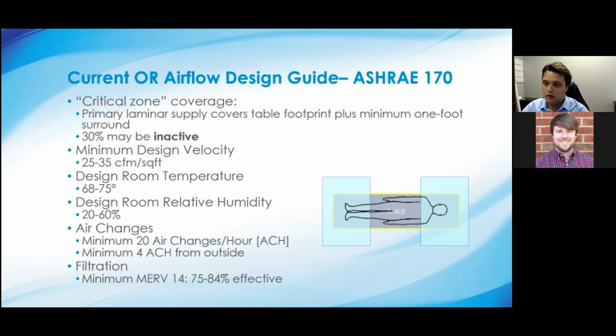Now, where did that 30% come from? How do you know that if you have 30% inactive, you're still safe? Honestly, your guess is as good as mine. I've never seen any backing of why 30% is acceptable, how that impacts patient safety or anything. It's kind of pulled out of a hat. That's the first point here, indicting the ASHRAE 170 code for not necessarily being best practice. It is a design guide. It is not a performance-based standard. That gets more evident when you start looking at some of these other points here.